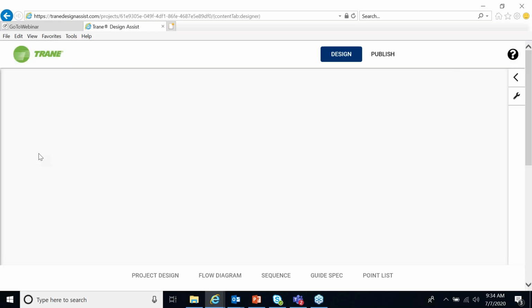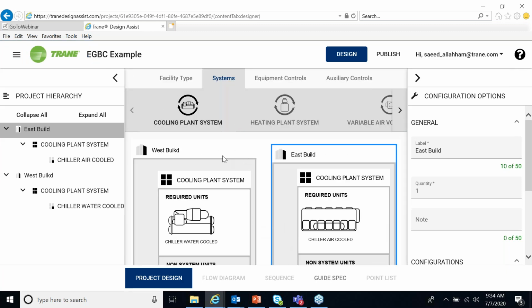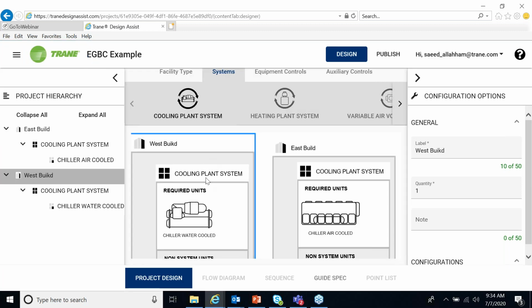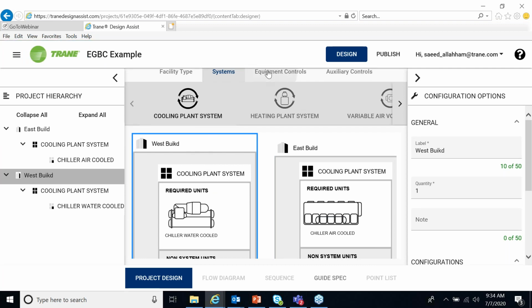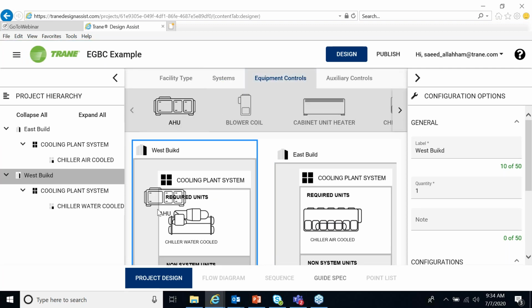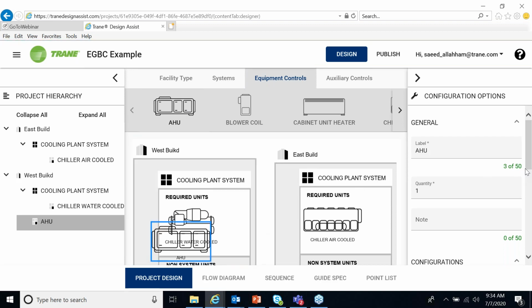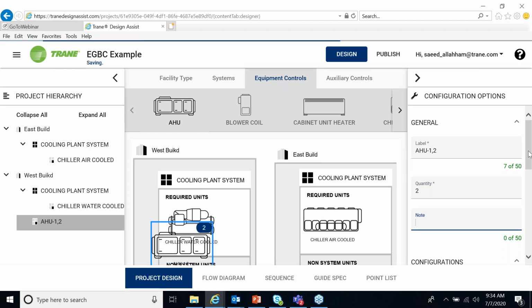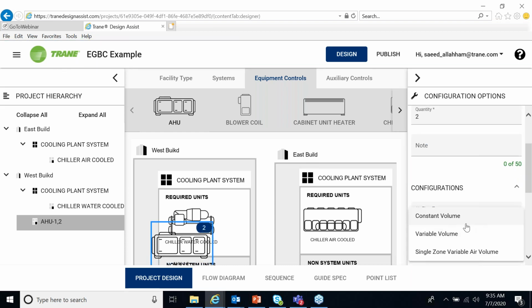Our project is the EGBC example. So we have here 2 buildings. Now let's look at the air side. For example, in the west building, we want to add an AHU. And we can select AHU-1, quantity AHU 1 and 2. Quantity we have, for example, 2 AHUs. Select the configuration of the AHU. It can be constant volume, variable volume, or single zone. Let's make it variable volume.